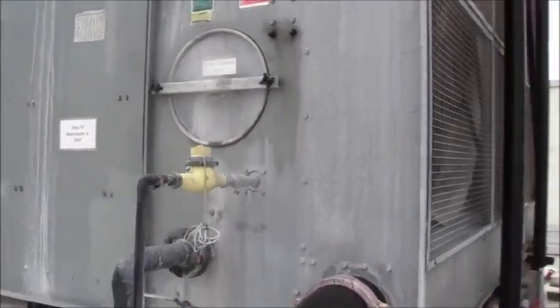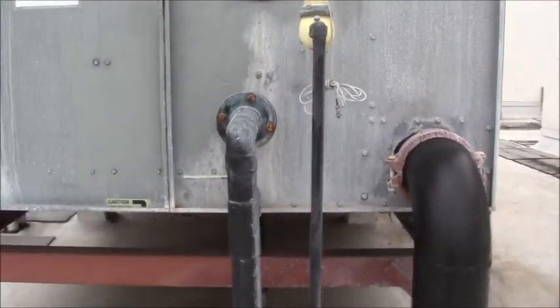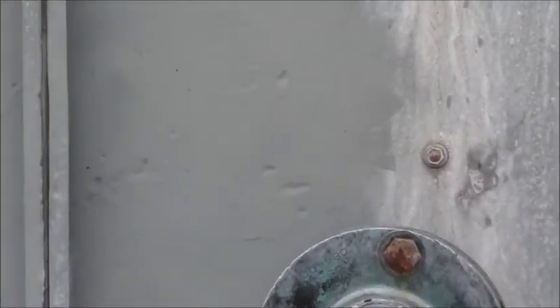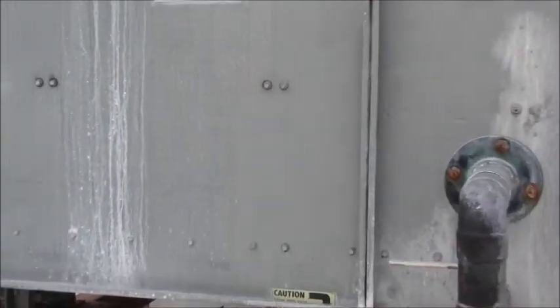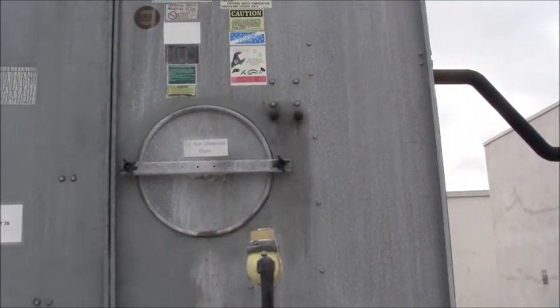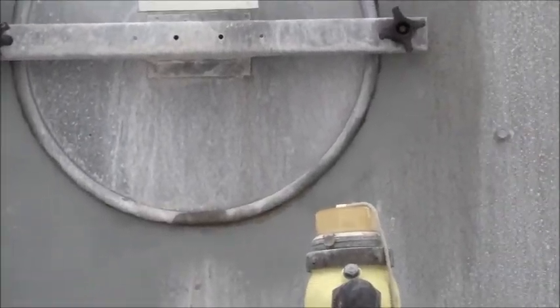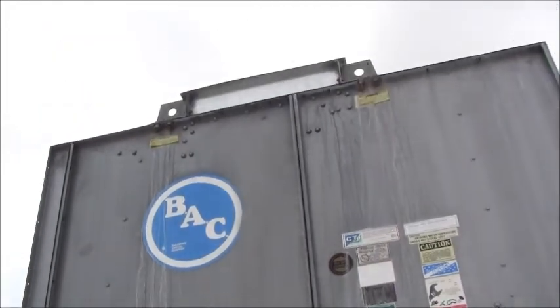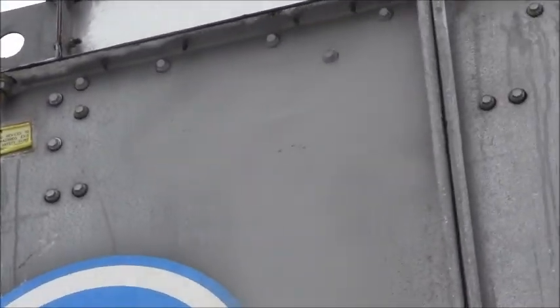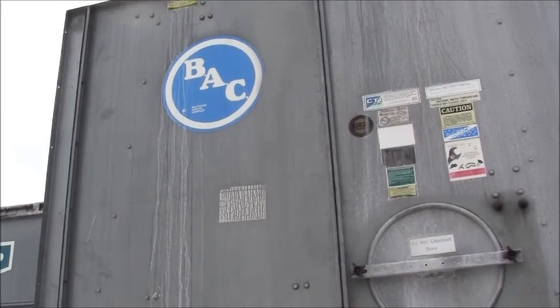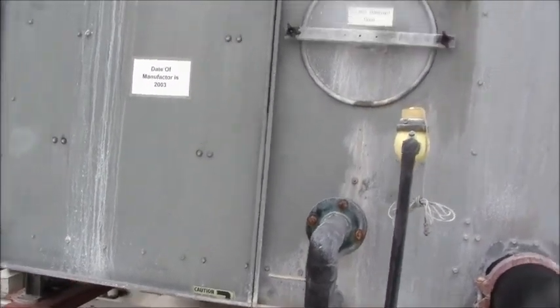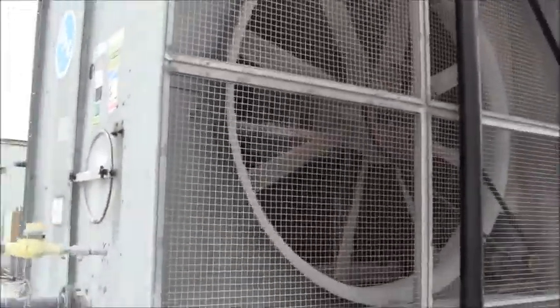So we're going to do this cooling tower next. Let me take you over here on the side of the cooling tower and show you the repairs that were made. There was a repair made right there, epoxy, then painted over with the zinc cold paint. Around the door, we had it done all the way around. That's all looking really nice. And if you recall, at the very top there, where is it? Right there, can't even see it now. We had made a repair there where it was broken through. I want to turn this cooling tower on so you can see the water running down on it, but I cannot do that right now.